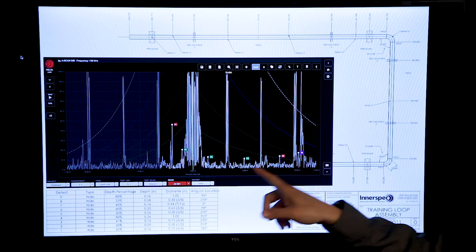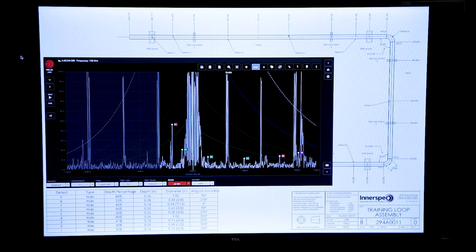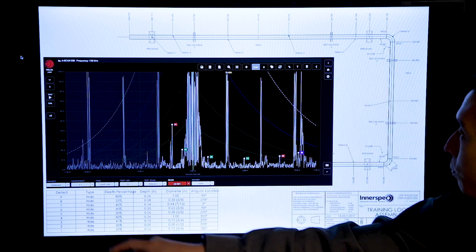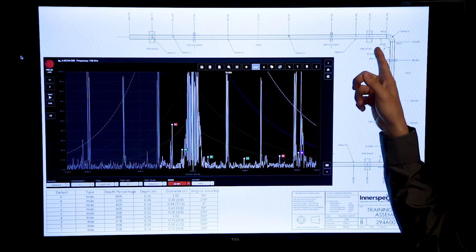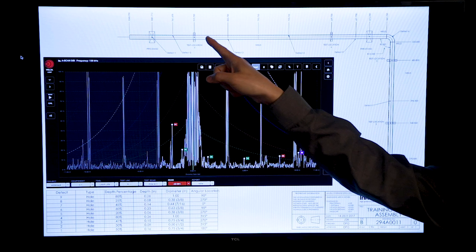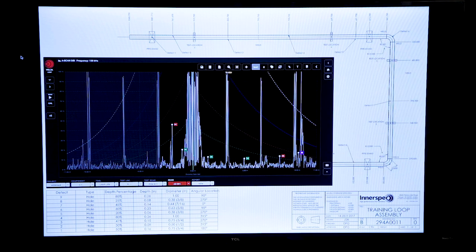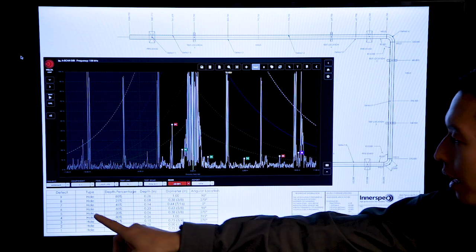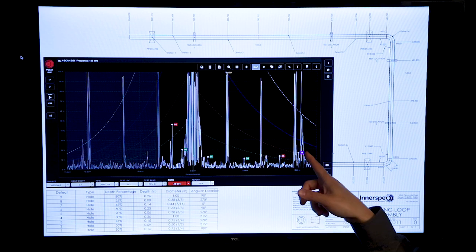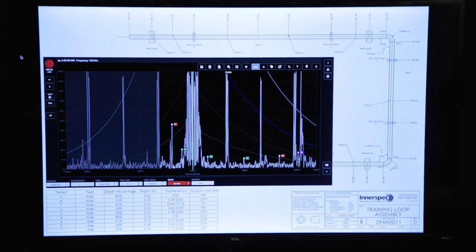We have the first weld of the elbow located approximately 32 feet away from the test location, and the second weld of the elbow located at 34 feet away. In between these two welds, there is defect 6, which is approximately 33 feet away from the test location. Defect 6 is 60% depth and 5/8 of an inch in diameter.